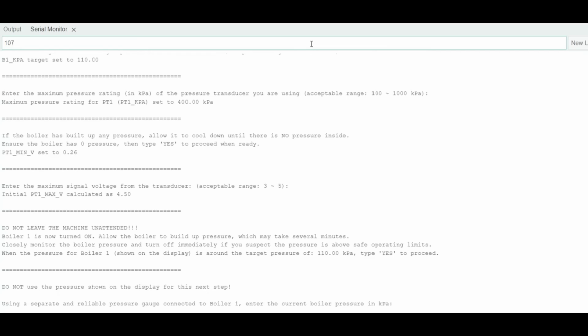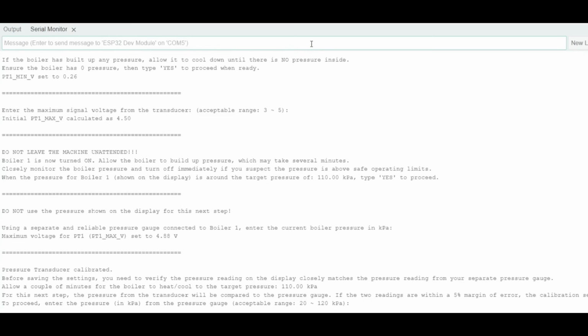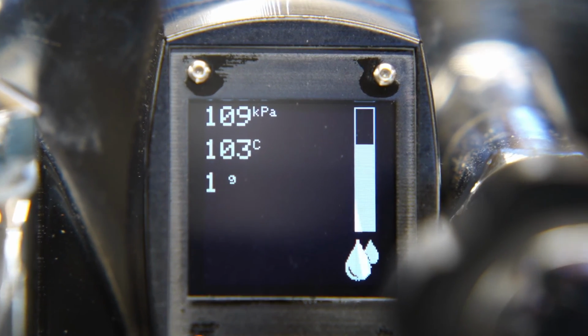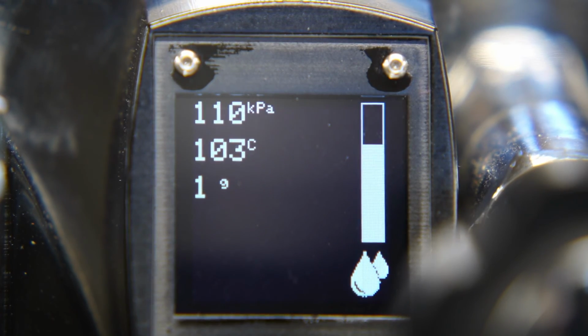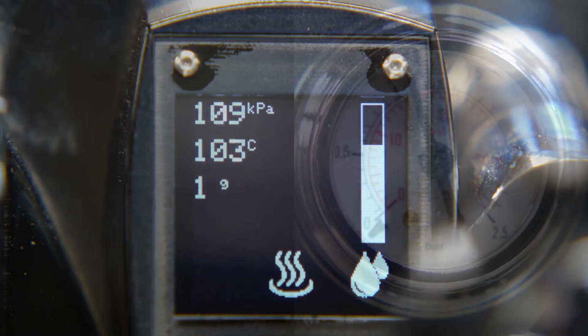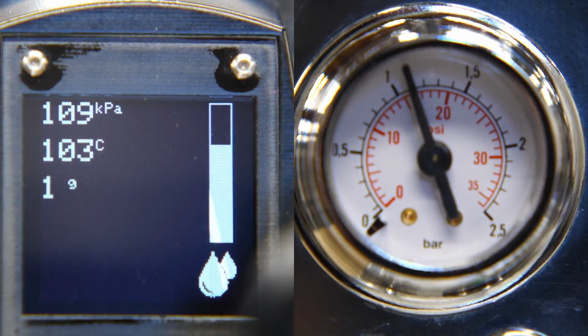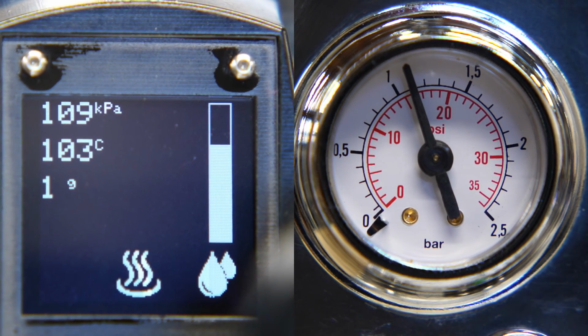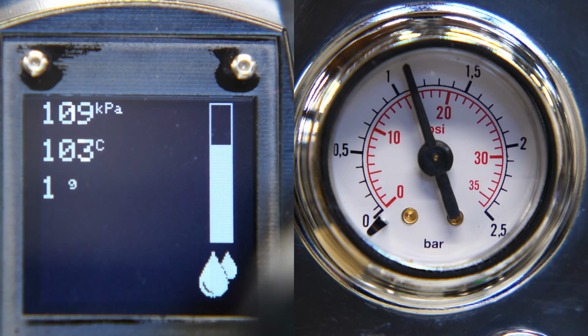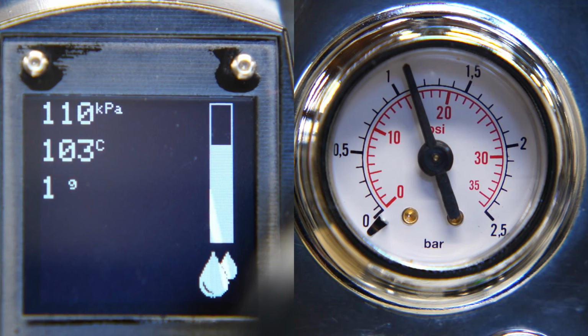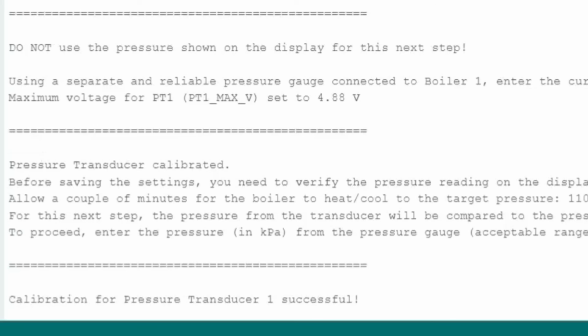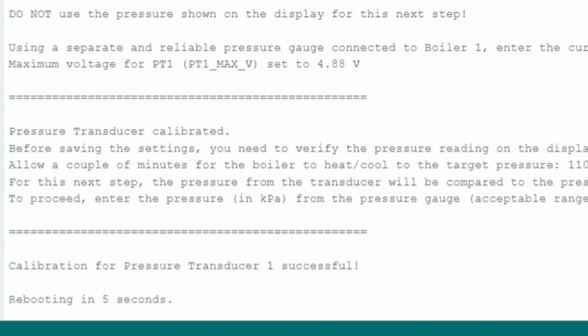The wizard now compares the pressure gauge reading I just entered and makes any adjustments if required. Now we're asked to let the pressure stabilize for a couple minutes using these newly calibrated settings. If we take a moment to compare the pressure on the display to the pressure shown on the gauge, we can see they are both reading 110 kPa now. The wizard is satisfied that the calibration has been successful and will now save and reboot.